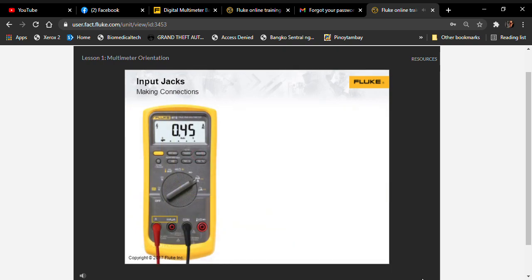Current measurements may be taken at one or two different inputs, depending on the meter. If there are two, then the maximum allowable current will be different at each input. If you're not sure what the current is that you're trying to measure, then it's best to use the higher rated input first. If the measurement is below the rating of the other input, then you can move the test lead over to get a higher resolution measurement.